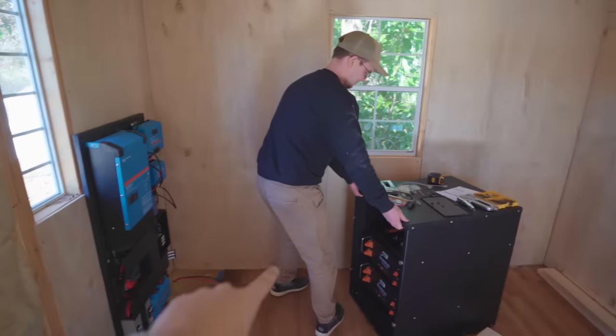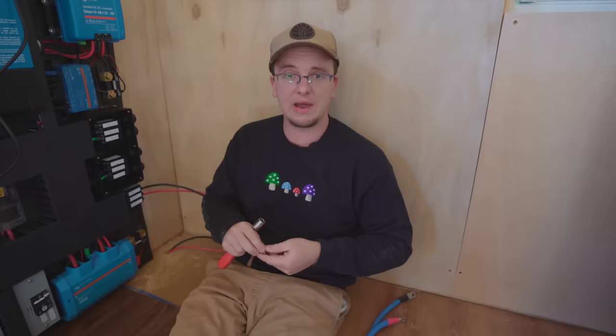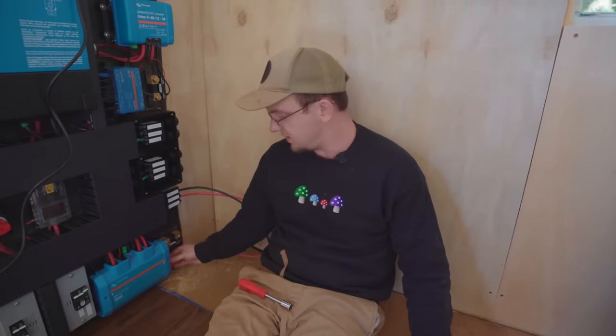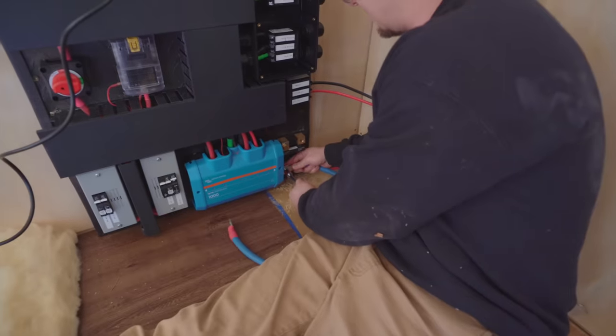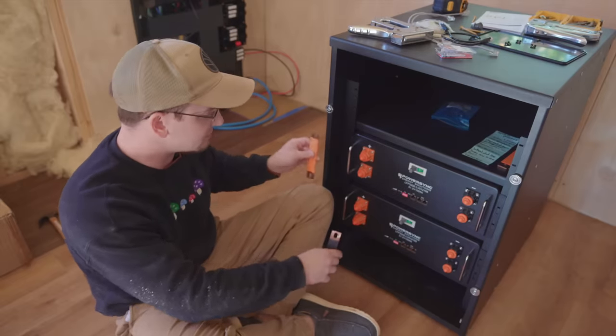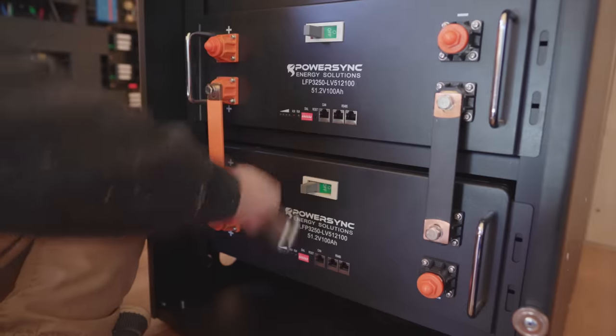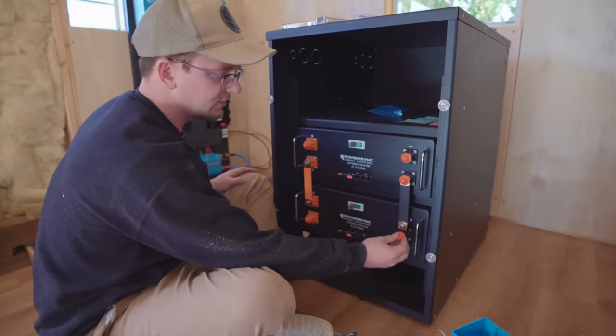Now we just scoot the battery box over. Yep. Actually, before we connect the batteries to the bus bars, we're going to connect these battery cables to the power board. So we are going to start with the positive cable right here, red. All right, let's get this tightened up. We need the batteries connected minus to minus, plus to plus. The batteries are switched to off, so there's no current coming out of the batteries. Orange is going on to positive. We'll put the protective caps back on.